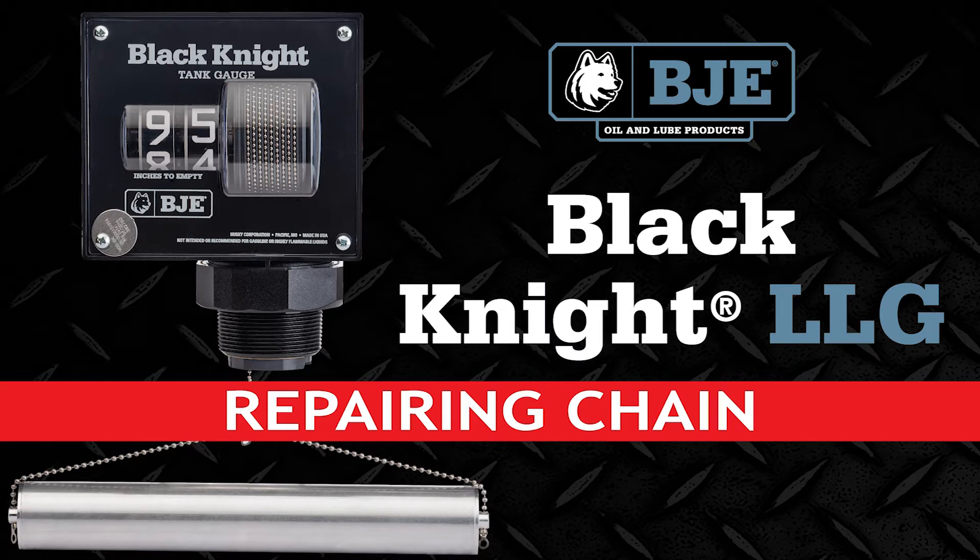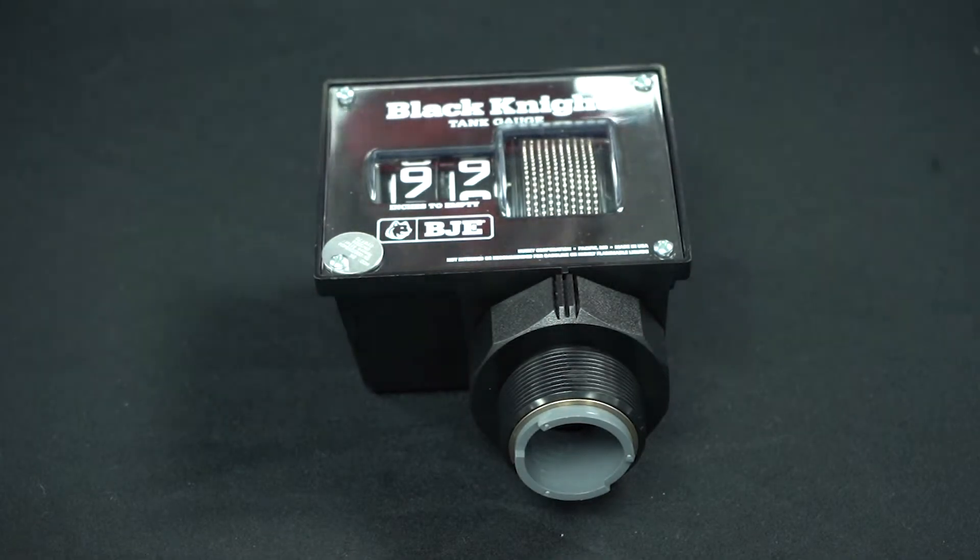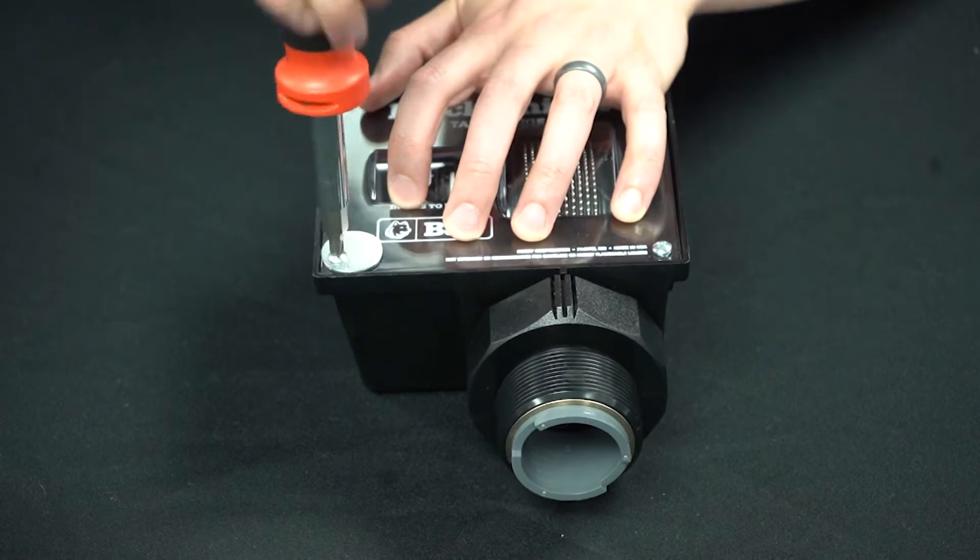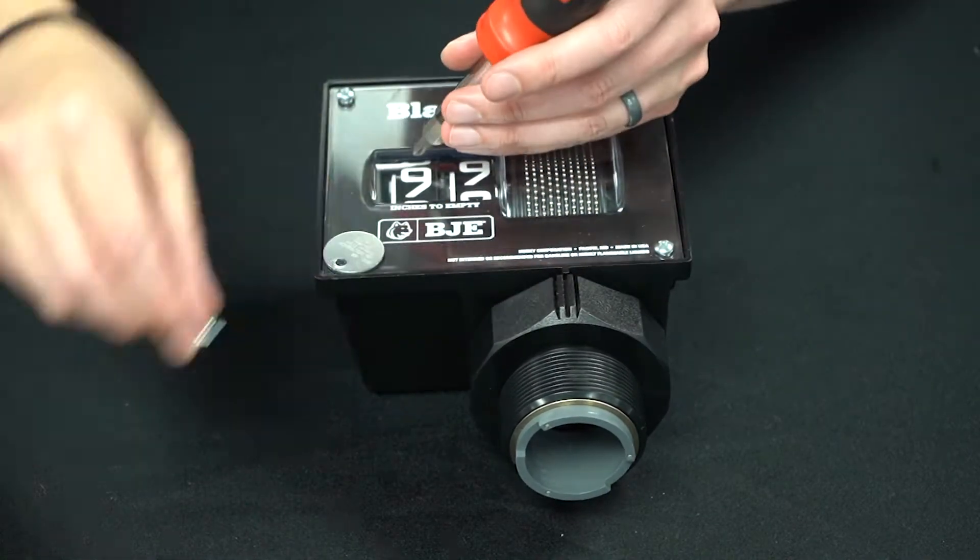This is a technical bulletin about how to repair a broken chain on your Black Knight tank level gauge. Remove the four screws, the cover, the face plate, and the gasket. Save those parts, you'll reuse them later.